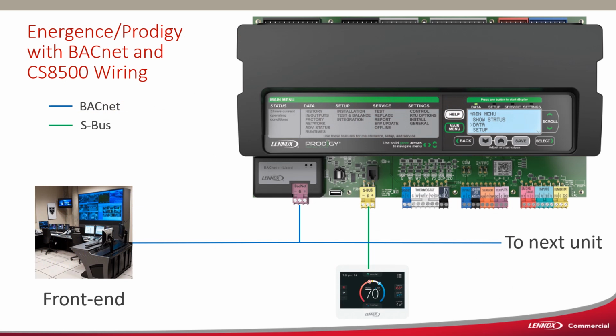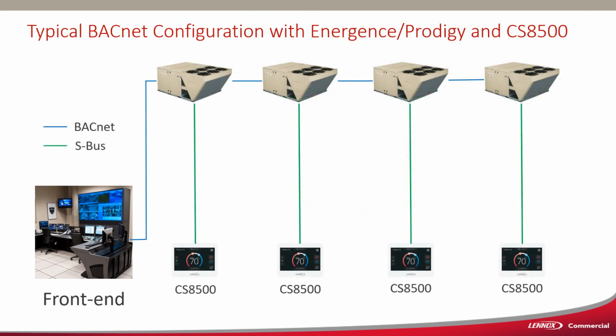This sensor slash thermostat is also BACnet capable, so you can put this on a system that has a BACnet. You order the Prodigy board or the package unit with our BACnet module. It can be factory installed or field installed. And you're going to wire your bus terminal straight to that module terminal. And then you're going to wire your sensor thermostat to the S-bus terminal. You're going to end up with a system that looks kind of like this, where you have a BACnet bus system, and then each unit has an S-bus going to the thermostat.